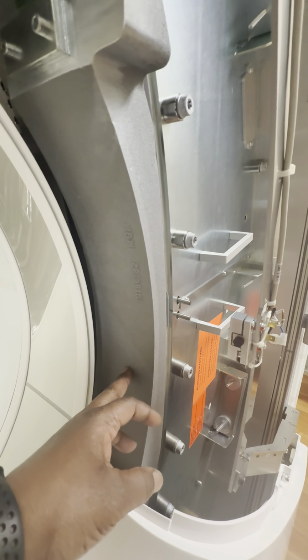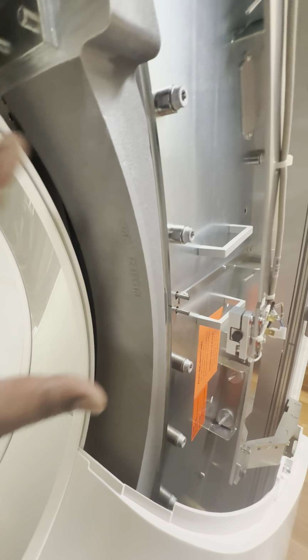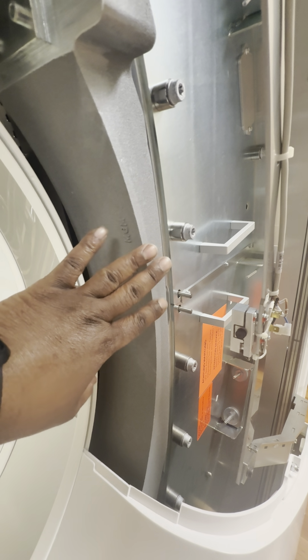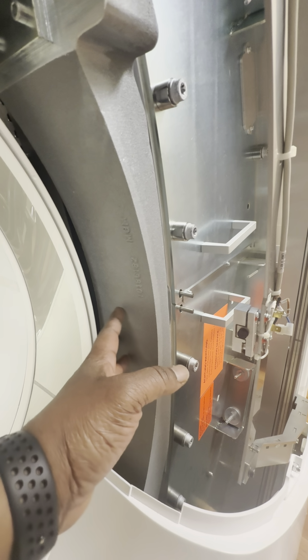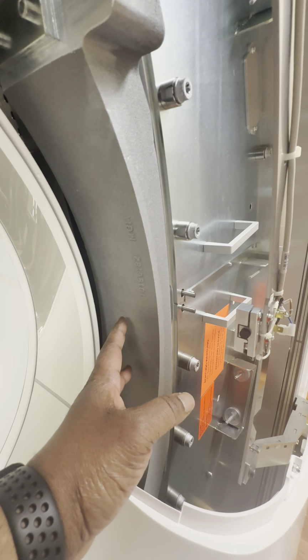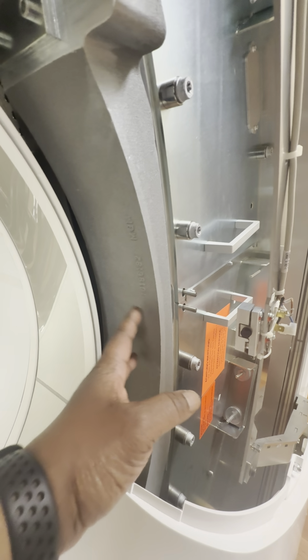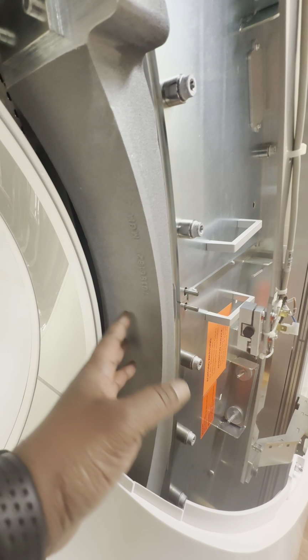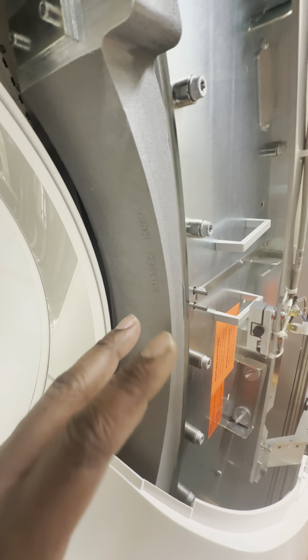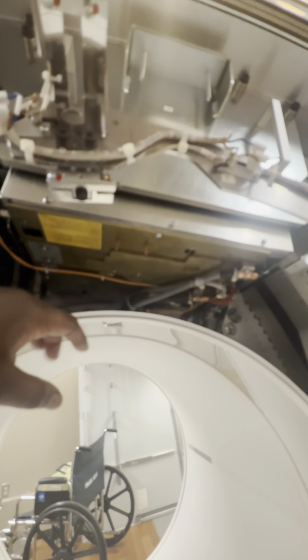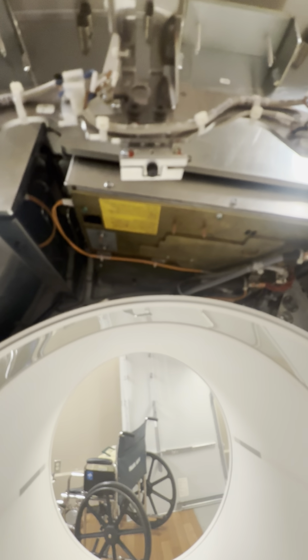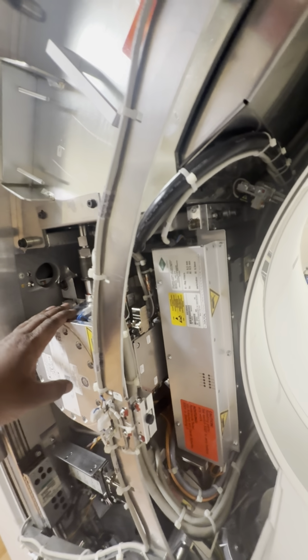Now this right here is a counterweight because they designed this to be balanced. On some systems, this will be replaced with what's called a UHR, or high definition receiver. It's like a screen that comes out to help the images be crisper, cleaner. This right here is the XGR, X-ray generator rotating. Now I'm using Siemens terms. With different CTs, they use different terms, but this is what Siemens calls this. This is what tells the tube to produce X-rays.